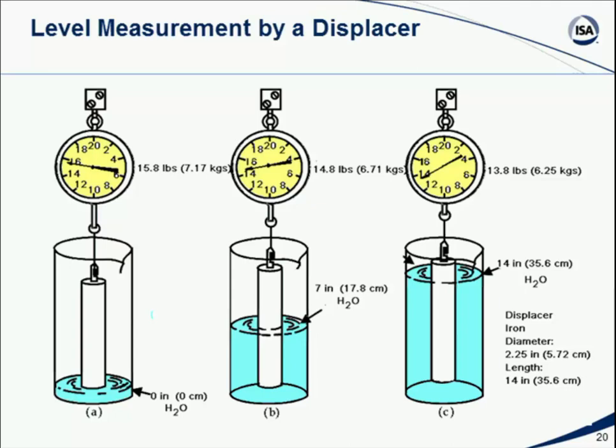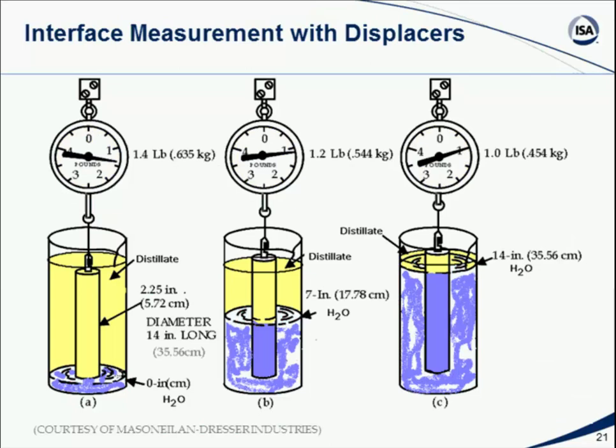Now, it may not be clear, but when the water level of the tank is all the way down to the bottom, you'd sit there saying, well, the displacer is just hanging there. Yes, it is, but it's actually not just hanging there in a vacuum. It's hanging there in air. Believe it or not, air has the same kind of buoyancy effect as any other fluid or liquid. It's just extremely small. So when we look at the weight of this displacer, we're actually measuring the weight of the displacer from fully submerged in air all the way up to fully submerged in water instead of air. Well, if we keep the same concept in mind, we can make an interesting use of a displacer.